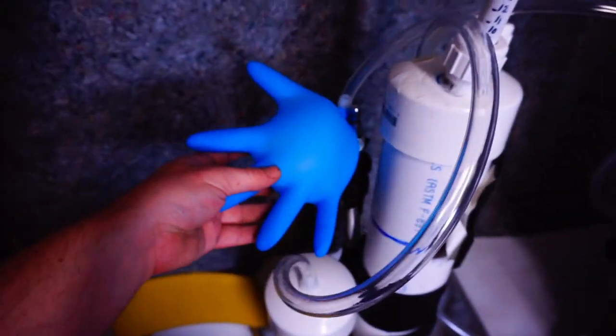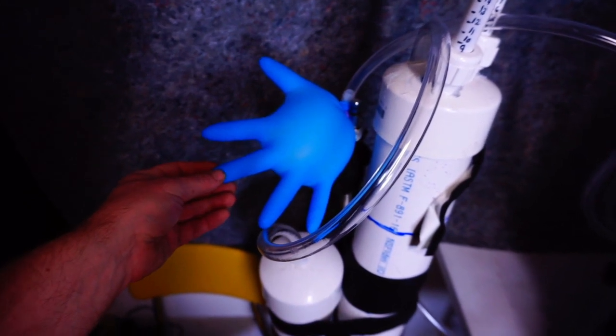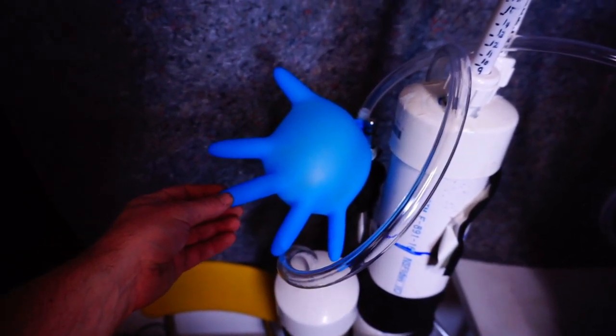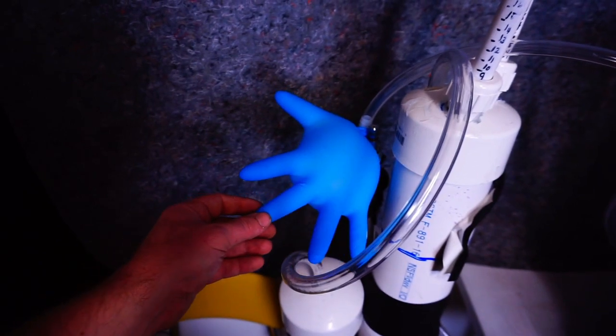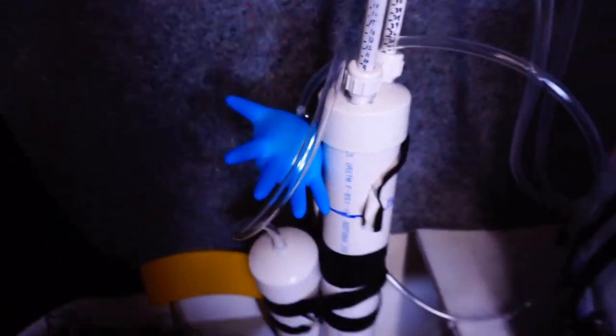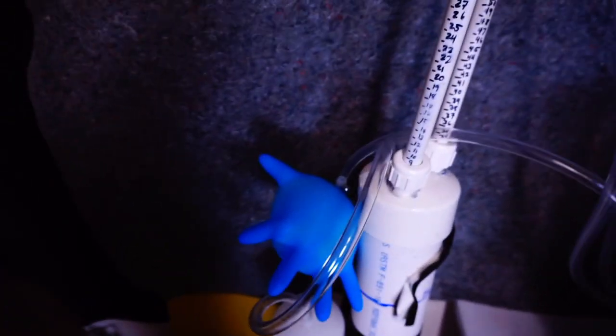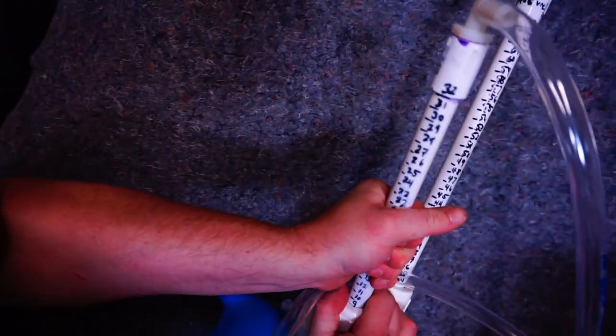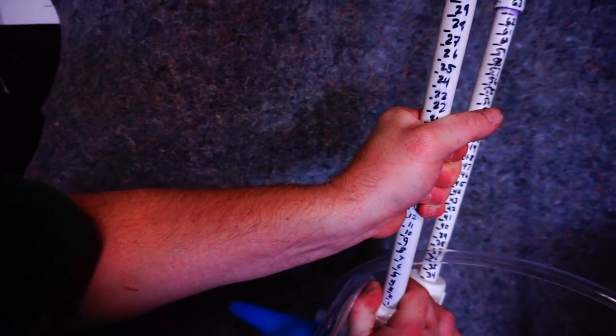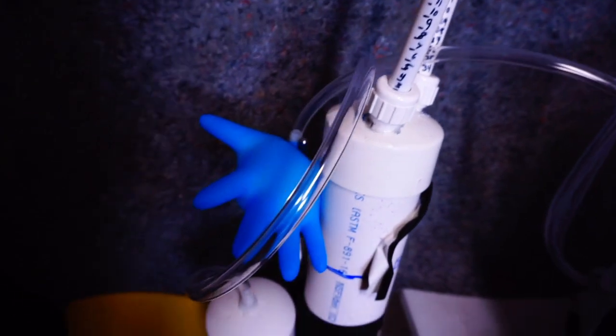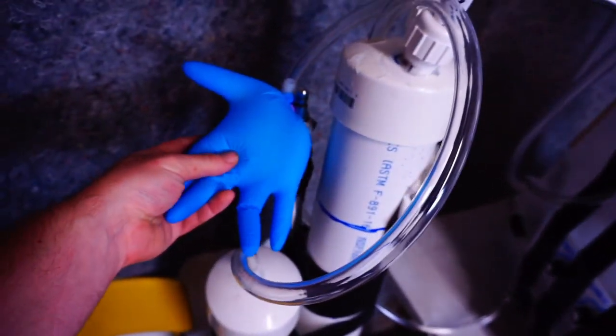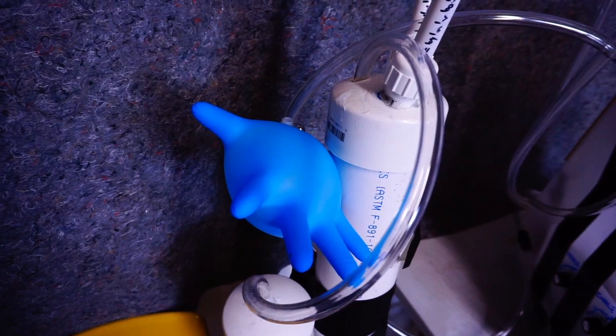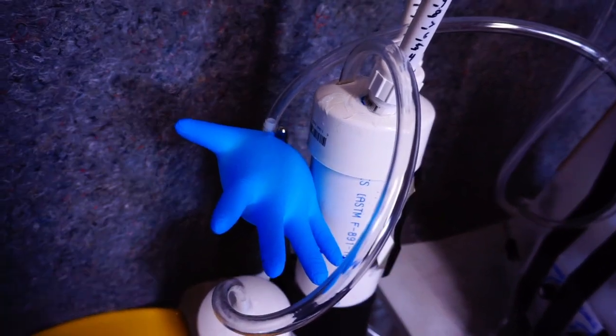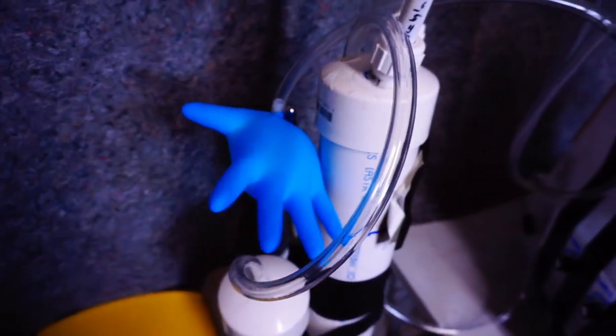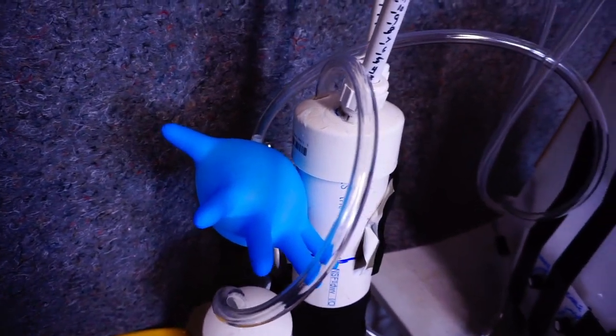Anyway, if we take a look, we're at 9 centimeters of PEEP pressure right now, and the glove does not really fully deflate. If I slide this, I've got to put the camera in my mouth for a second. Now we're at about 3 centimeters of PEEP, and we can see that the glove deflates pretty well during the exhale cycle. Pretty low pressure in that glove. Not the best test lung, but it's okay.